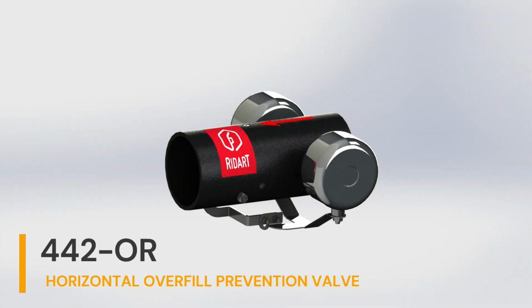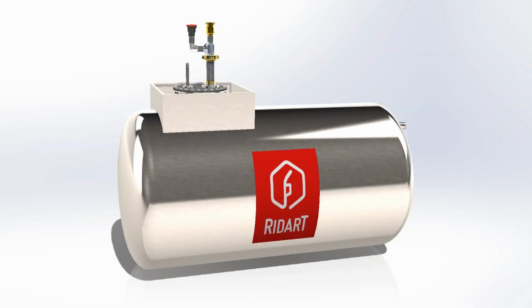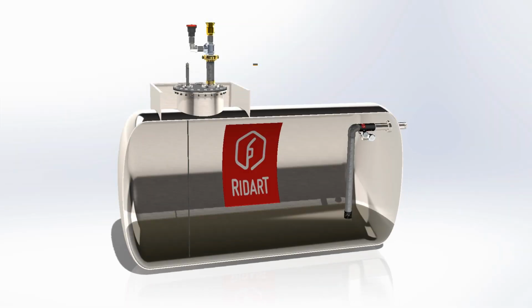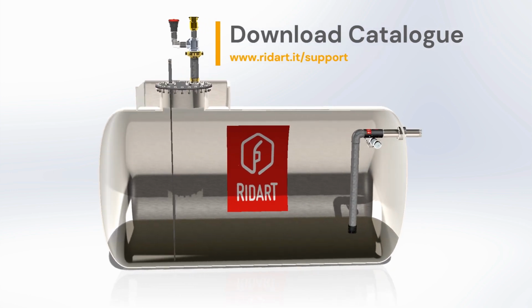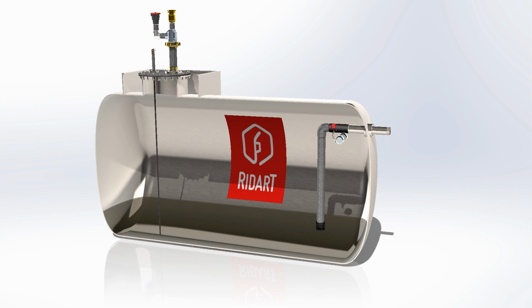This video will describe the working principle and installation guide of the Horizontal Overfill Prevention Valve, indicated in our catalog as Figure 442 OR. The Horizontal Overfill Prevention Valve is usually installed in fuel storage tanks with a lateral fuel intake, as represented in the video. Alternatively, it can also be installed on the manhole.